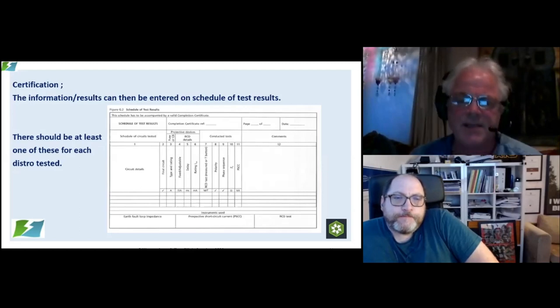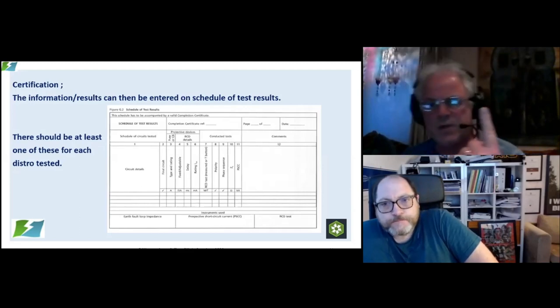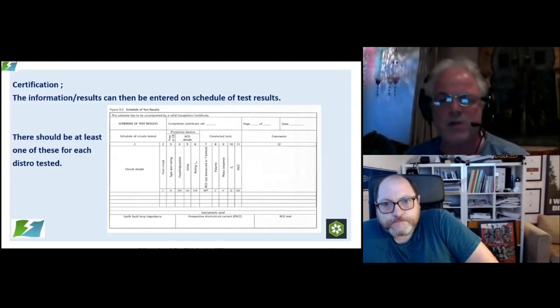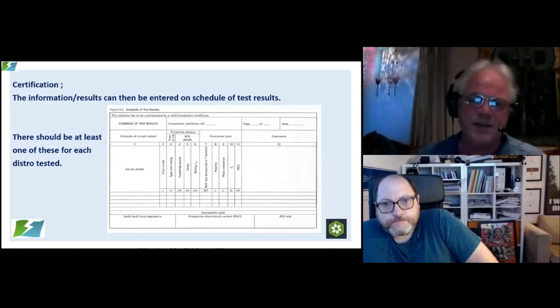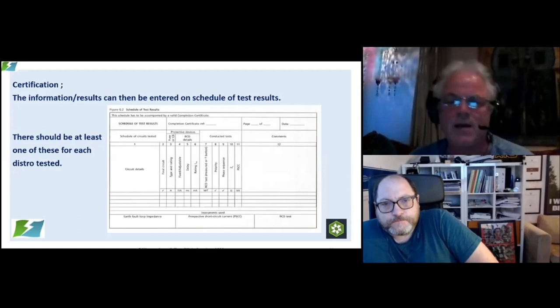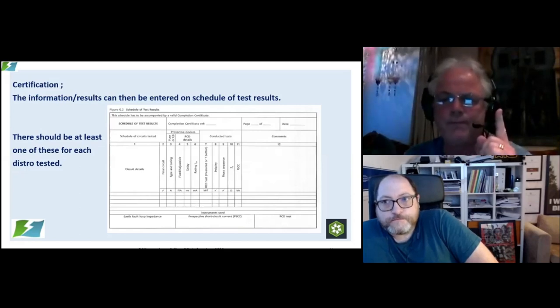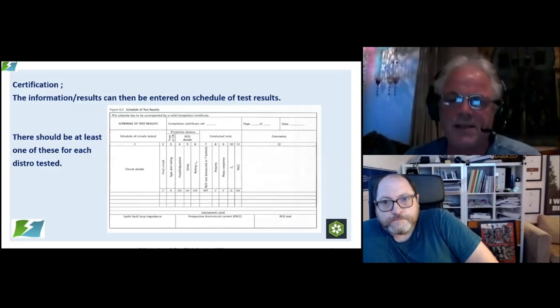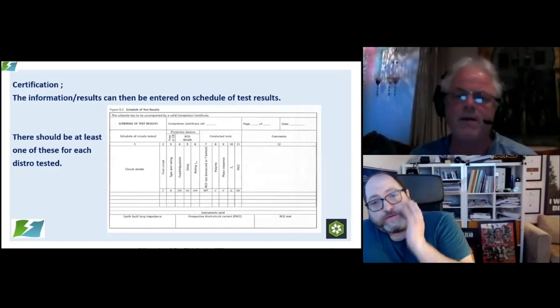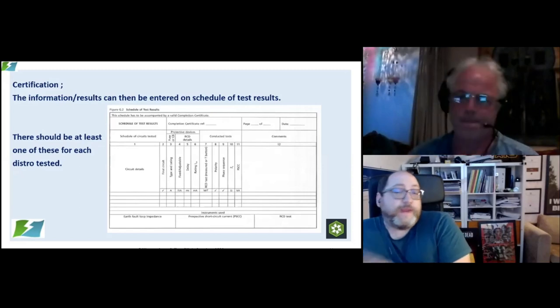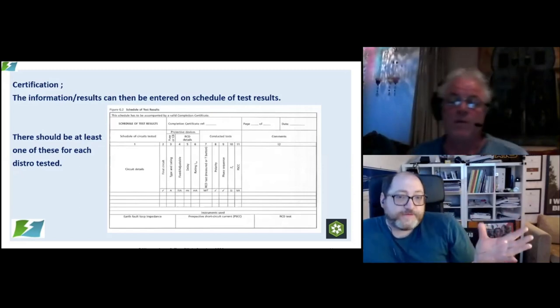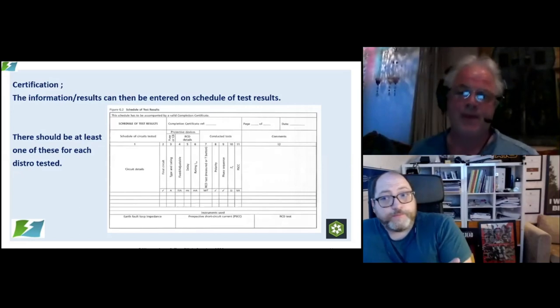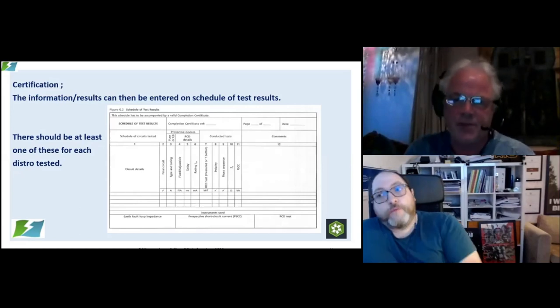The RCD test itself, is it done by touching the test button, or is it done by measurement using a test meter? The rating of the RCD, the delay of the RCD. So a very, very minimal amount of testing. An RCD test is normally using the push button. Yeah. If you've got a selectable RCD, then I will test it using an RCD tester to make sure I've done the setting right. Continuity and insulation have all been carried out at the pre-check of selection of all of the distribution equipment, back at base. So we don't have to do that on site.